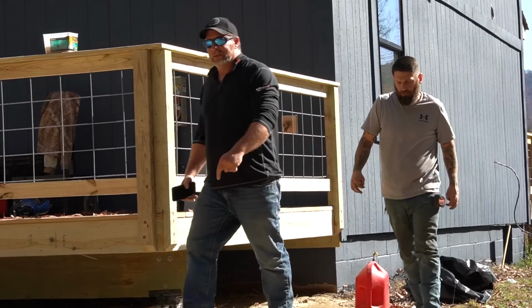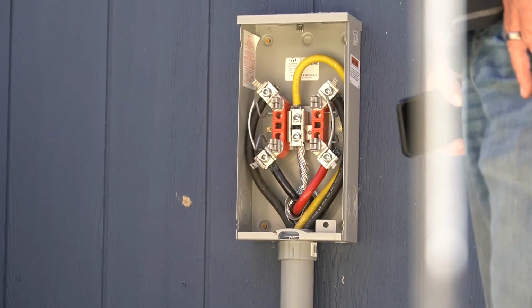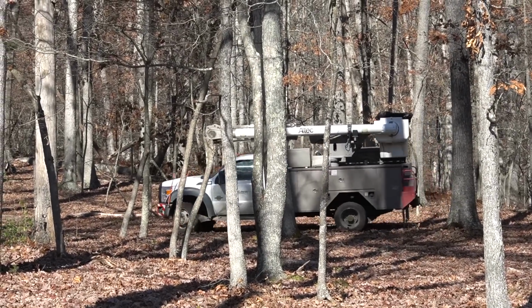As you guys know, we've been without power for a few months now at the renovation house, and we're really excited about getting power turned back on. The power company came back there to put the meter in there. No power. If you all do remember that we dug up the wire because we thought we may have hit it, and we confirmed we did not hit it. So we had our fingers crossed, power's getting turned back on, inspection was done, ready to go, and there's no power. The power company checked their transformer is functioning and working. Somewhere in between the meter socket and the transformer, the line's cut.